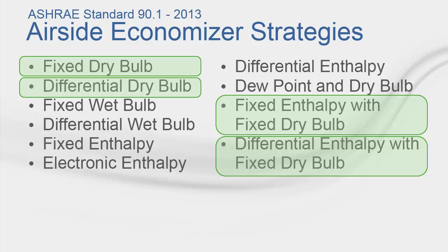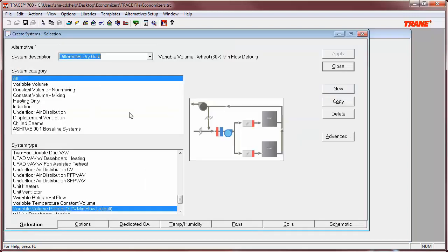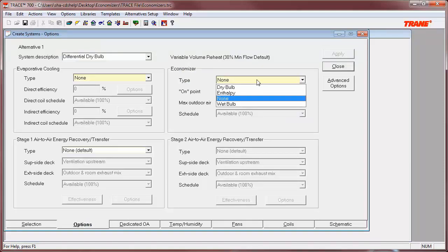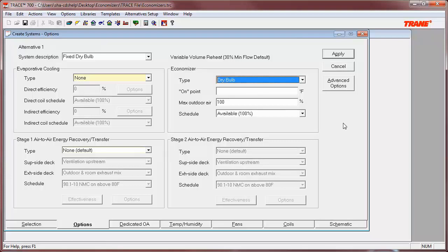We will now take a look at how to model these economizer control strategies in TRACE 700. Modeling the fixed dry bulb method is fairly straightforward. Users will simply navigate to the Options tab of Create Systems, select the system to which the economizer will be applied, and select Dry Bulb as the type. Users will then have to set the on point, or high limit shutoff, which is the point at which the economizer will be disabled and only mechanical cooling is used.